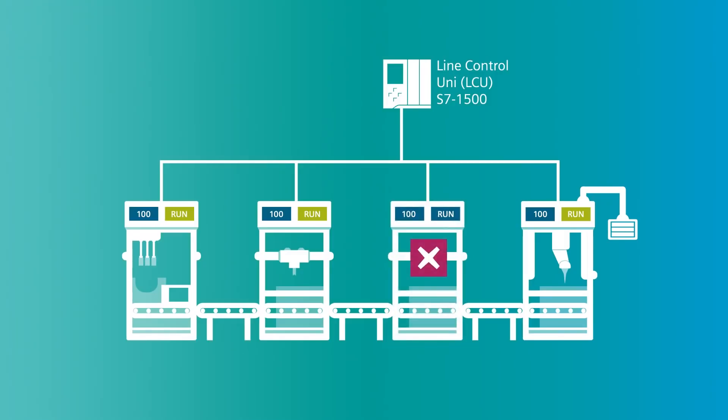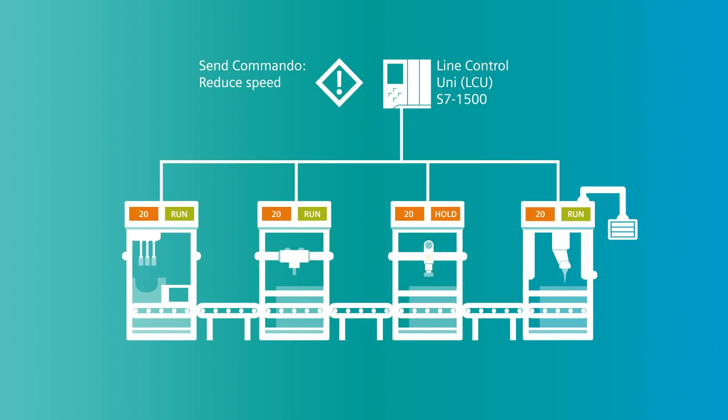No further work needs to be carried out on the individual machine. The final step involves centrally controlling and synchronizing all machines on the line. For this, we'll use the practical concept of a Line Control Unit, or LCU for short. A separate SIMATIC S7-1500 becomes a full-featured line controller with this application. The LCU knows the OMAC status model and can operate all machines which work according to this status model. Four different strategies for controlling the line are available to the LCU, depending on the application.